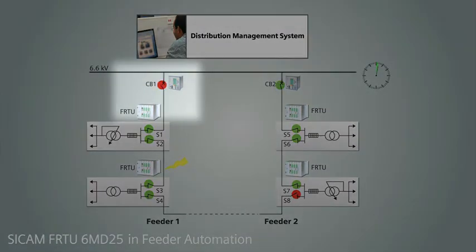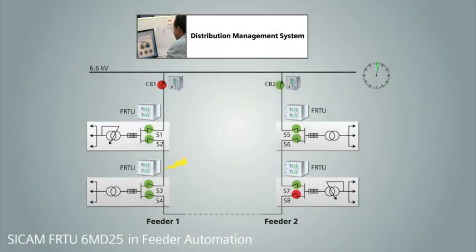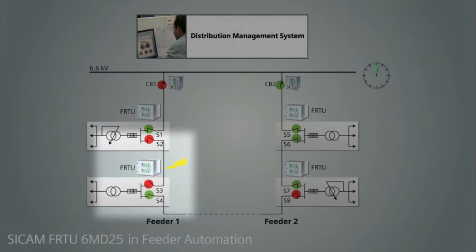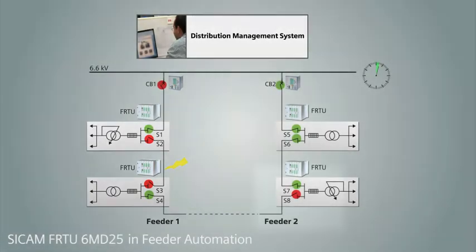The feeder gets disconnected. Switches S2 and S3 are opened and switch S8 is closed by respective FRTUs. Once the fault is isolated, feeder 1 is closed with quickest restoration of service with merely no effect on consumers.